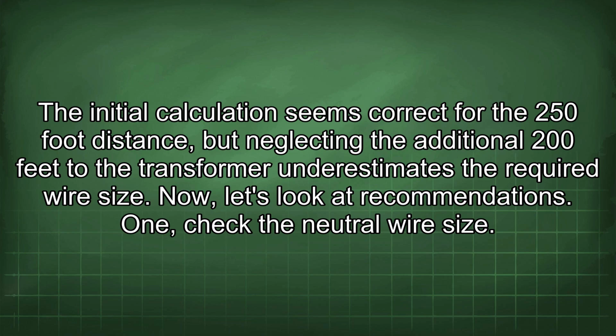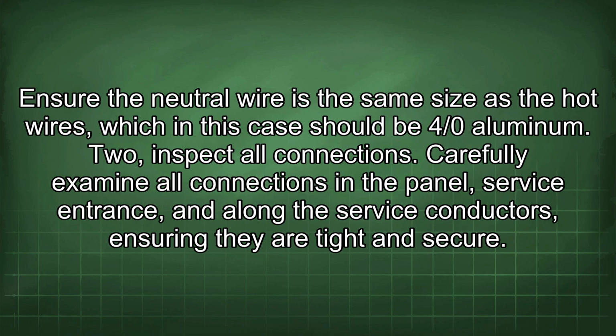1. Check the neutral wire size. Ensure the neutral wire is the same size as the hot wires, which in this case should be 4/0 aluminum. 2. Inspect all connections. Carefully examine all connections in the panel, service entrance, and along the service conductors, ensuring they are tight and secure.